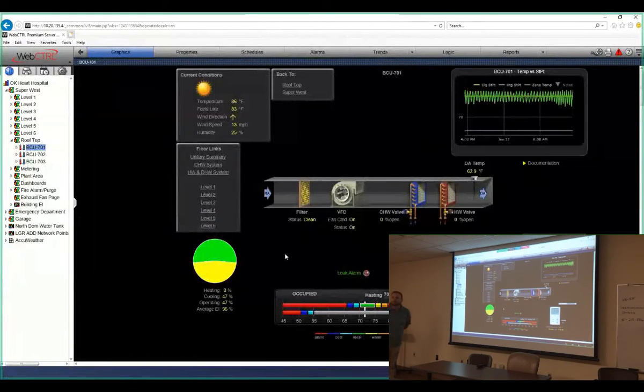Are all those leak alarms in the pan underneath them? They're in the unit, underneath the pan. Gotcha. So right now, we're probably going to change that. We're going to get them a device that's going to screw in the side for a condensate overflow switch. So there's going to be a wet switch on them that shuts that unit off when it senses it? Yeah, shut the valve off. We'll leave the fan running.